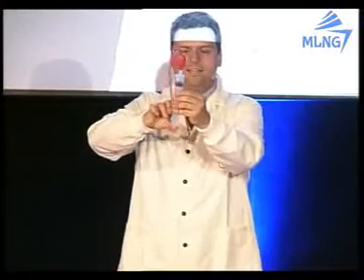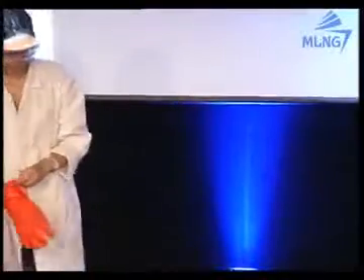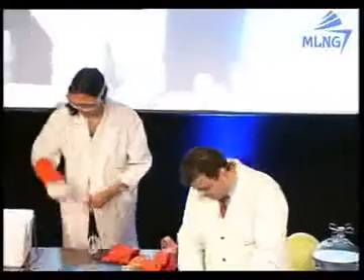So if we don't want to vent the gas, there is a very clever way of controlling the pressure when you fill up a tank. It's very clever. And so this is the tank. And if we want to control the pressure, the idea is to cool down the gas phase. Let's see if the camera can come here.